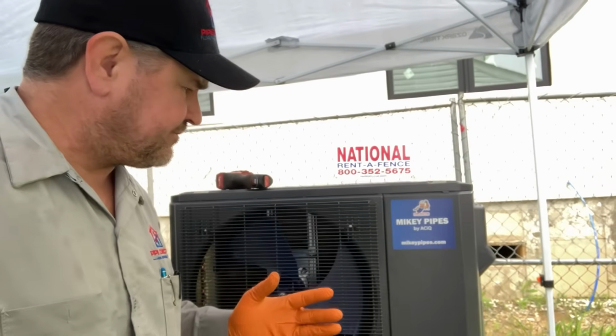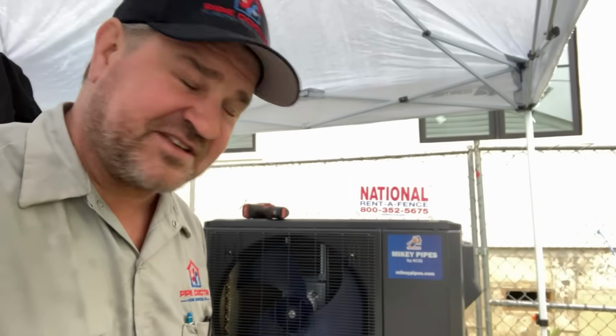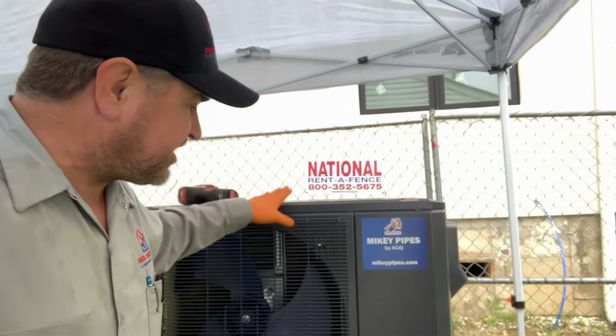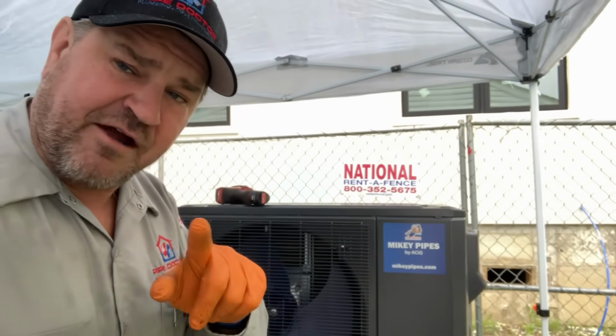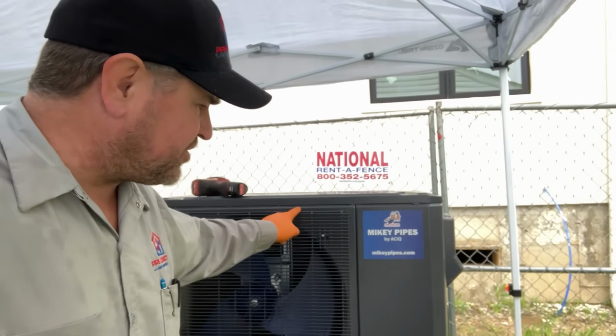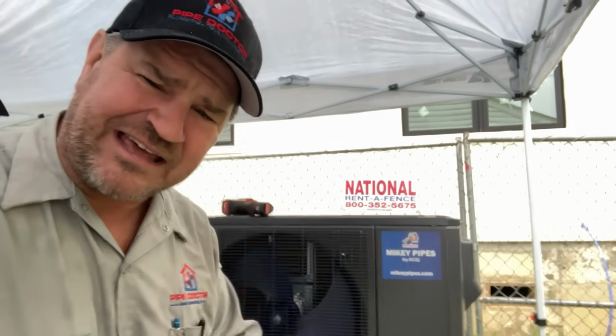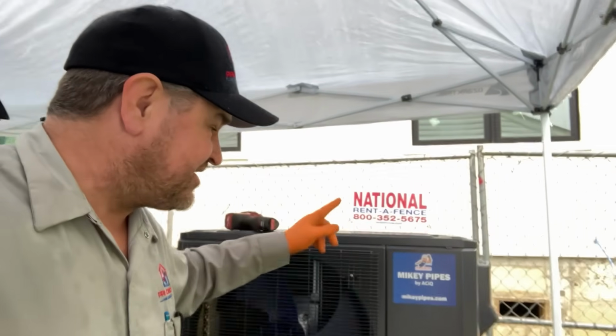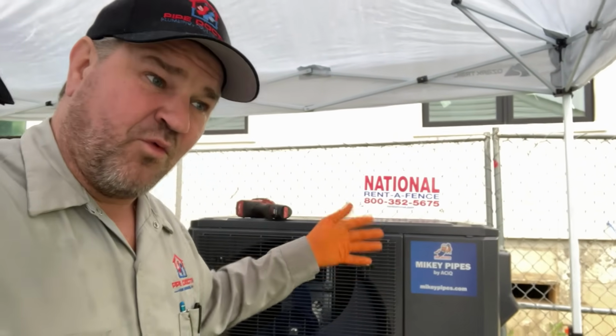It's communicating. Let's say they still want to use their Nest or Sensi thermostat, or even their Honeywell 9000 or T10, for example—you can still communicate from the indoor air handler to the outdoor condensing unit with just 2 wires, and still utilize the R, W, Y, G, and OB wires to your existing thermostat. You can still keep that thermostat, or use the one they offer. Wi-Fi and non-Wi-Fi models are available.